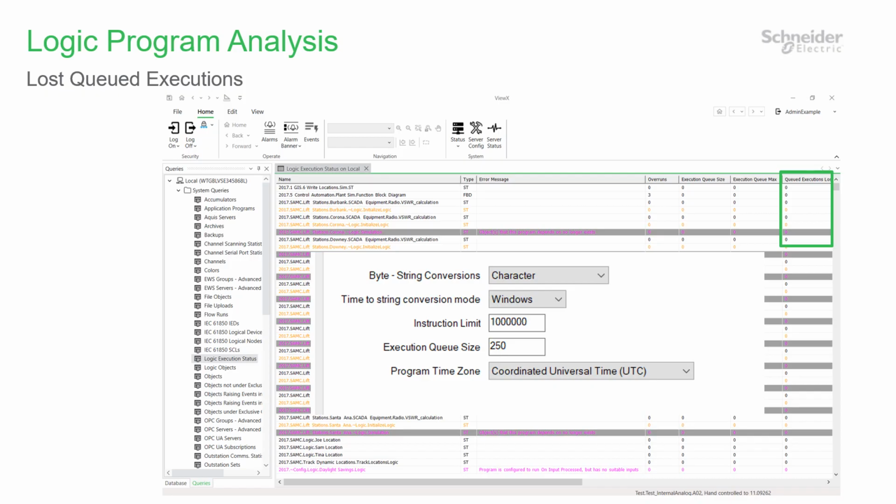You can increase the queue size, but that won't decrease the loading. So consider making some of the input variables no cache so that fewer inputs will cause queue execution, and reduce the queue size to 1 so that only the latest inputs cause a fresh calculation.